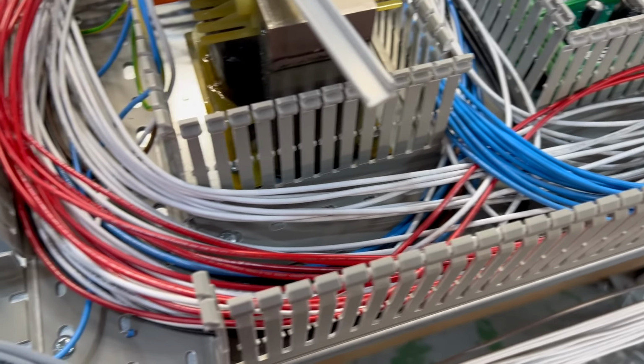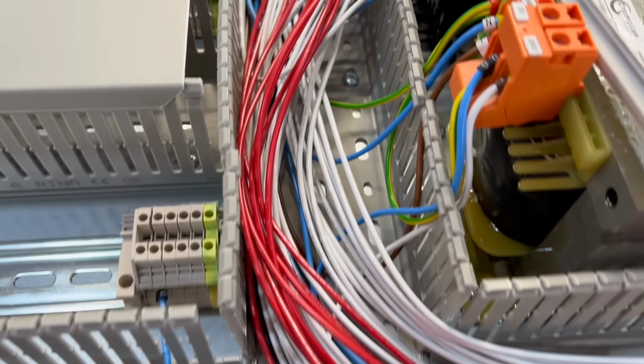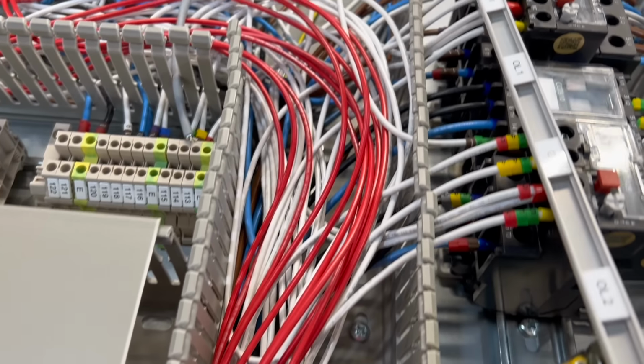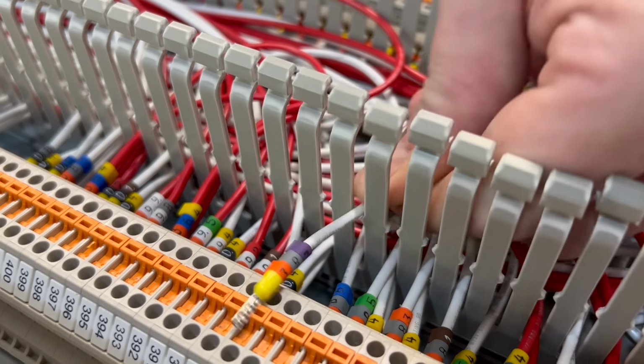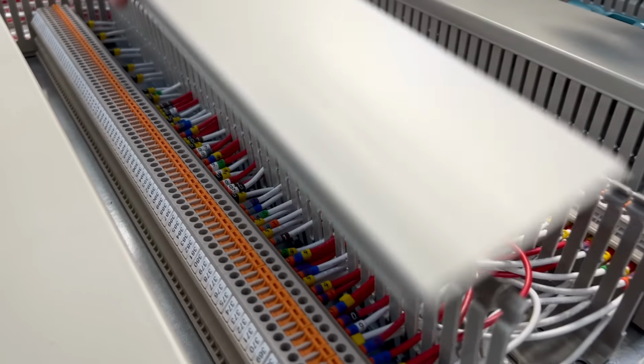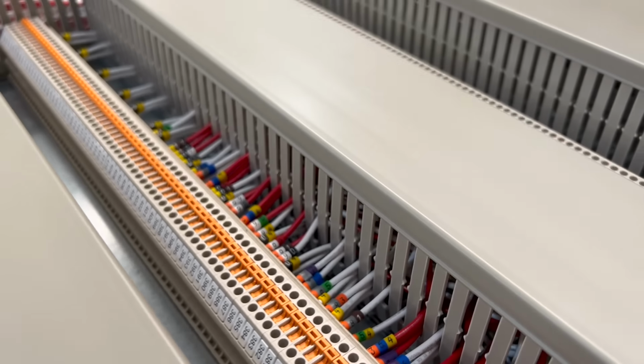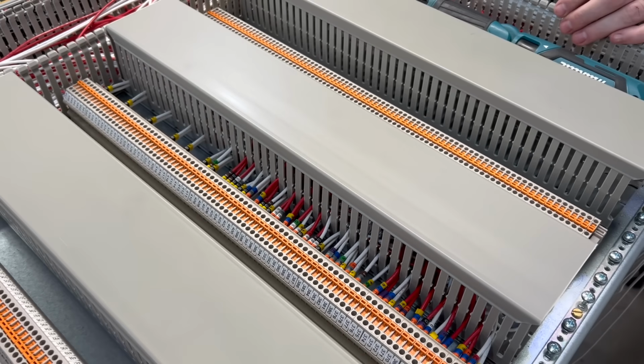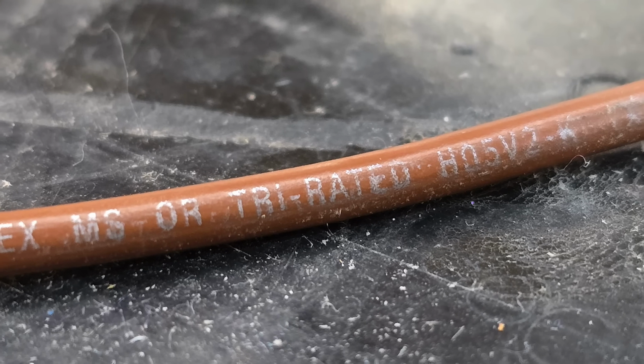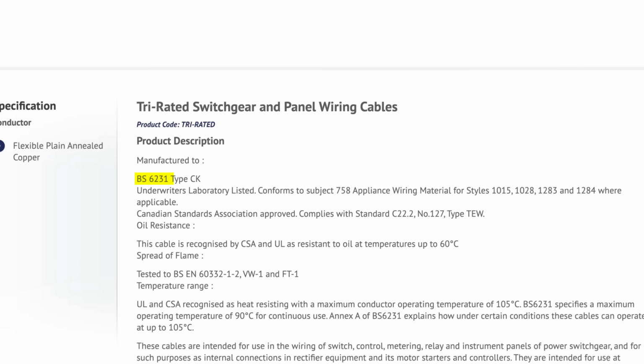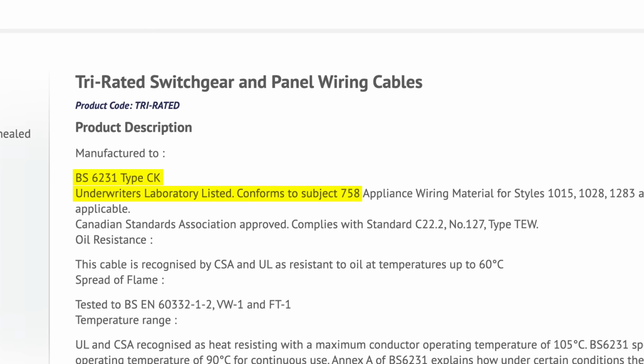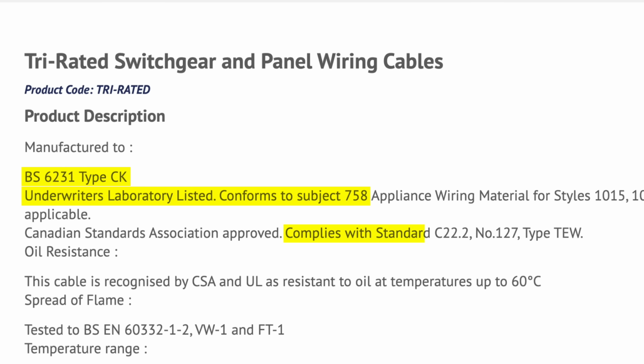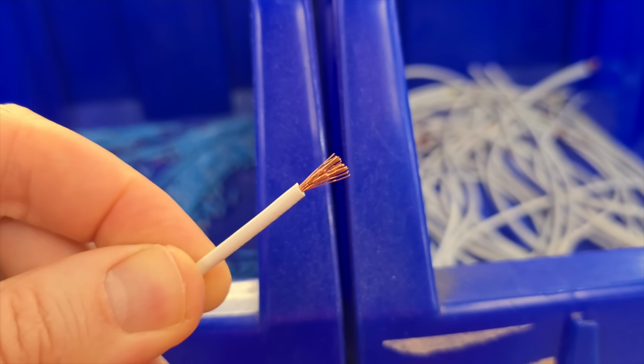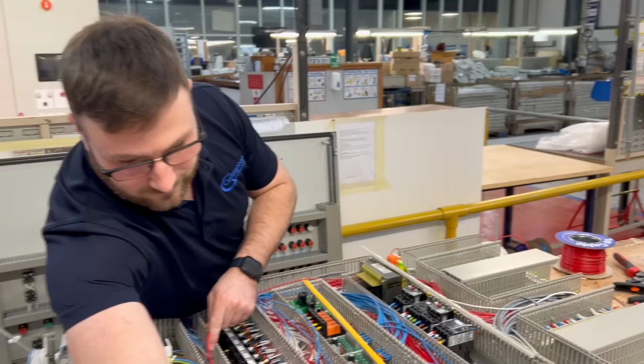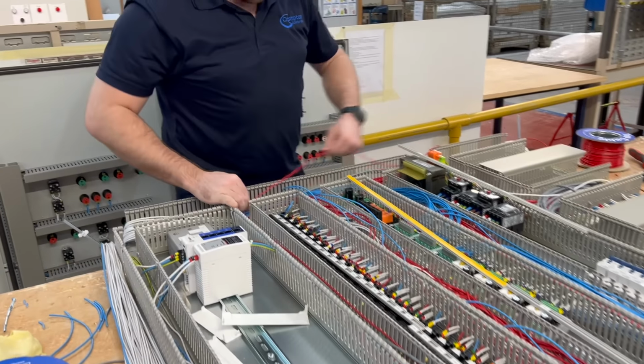Moving on from the isolator, we can then trace the wiring around. These are run through slotted trunking like this, which is cleverly designed to allow cables to enter and exit the trunking through the top during manufacture, and then the lid holds them in place once it's snapped on. The wiring used in this type of construct is usually tri-rated, so called because it complies with three different standards: BS 6231, which is British, UL 758, which is the standard in the US of A, and CSA 22.2 from Canada. It's a fine stranded cable and falls into class 5 under the British standard, and is therefore flexible and perfect for use in a control panel.